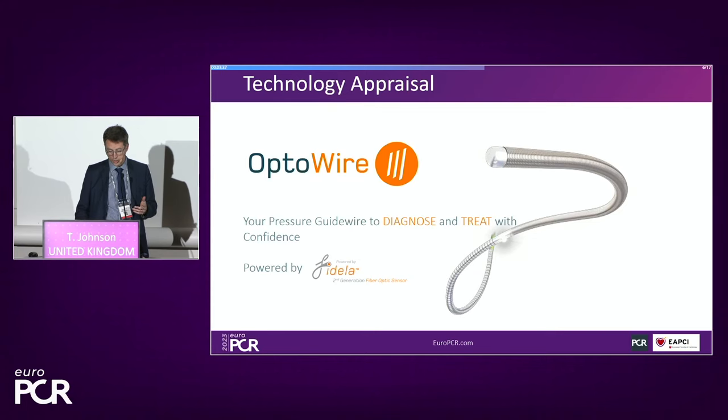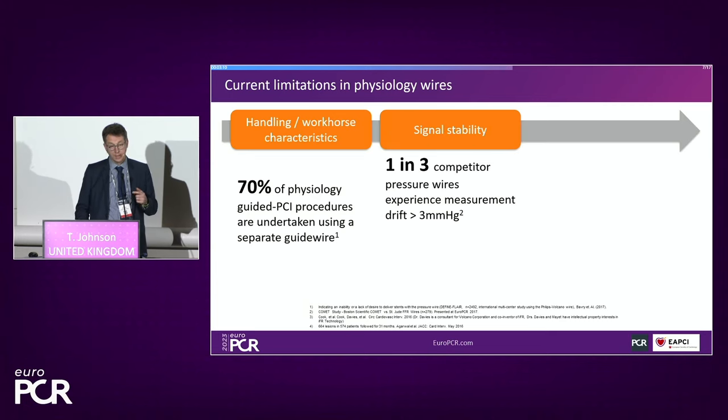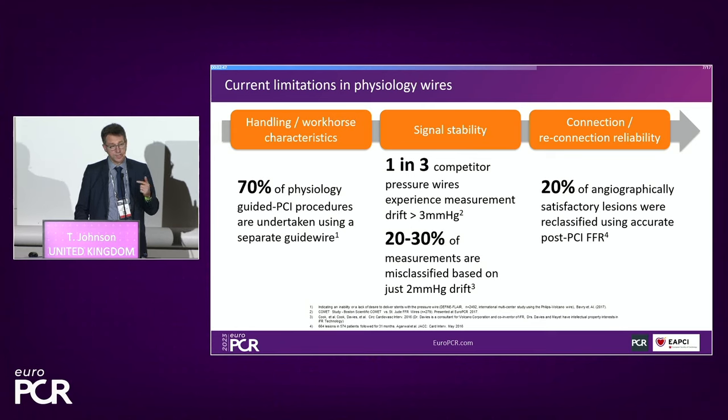The OptoWire is the next-generation wire. I performed this DK crush using the Opsens wire throughout the procedure, taking multiple assessments — you can connect and disconnect — which allowed me to continuously assess the impact of my intervention, finishing with 0.93 in both limbs. It behaves like a workhorse and has excellent stable signal stability, something not well maintained in competitor wires, with one in three competitor wires showing significant drift. Even two millimeters of mercury drift can result in a significant inappropriate measurement of physiology.